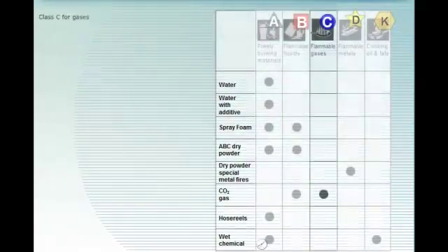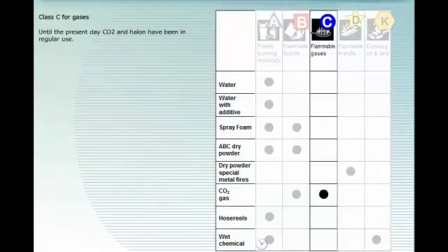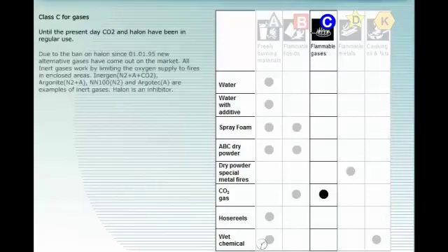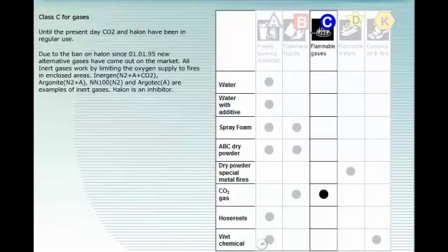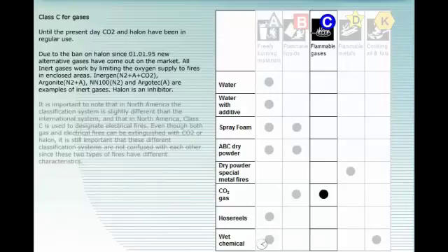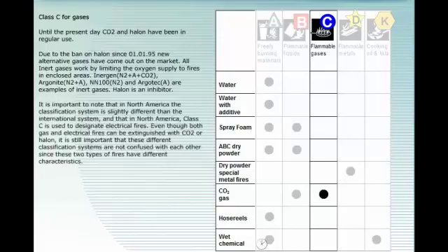Until the present day, CO2 and halon have been in regular use. Due to the ban on halon since the 1st of January 1995, new alternative gases have come out on the market. All inert gases work by limiting the oxygen supply to fires in enclosed areas. Inergen, Argonite, NN100 and Argotec are examples of inert gases. Halon is an inhibitor. It is important to note that in North America the classification system is slightly different than the international system, and that in North America, Class C is used to designate electrical fires. Even though both gas and electrical fires can be extinguished with CO2 or halon, it is still important that these different classification systems are not confused with each other, since these two types of fires have different characteristics.